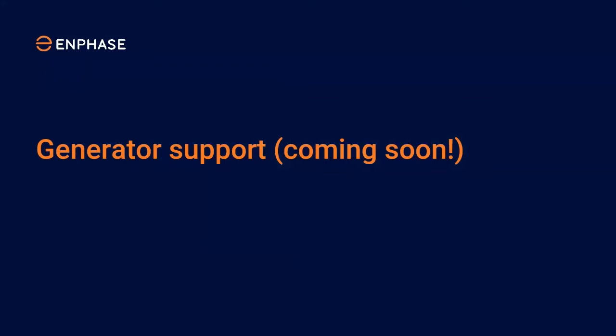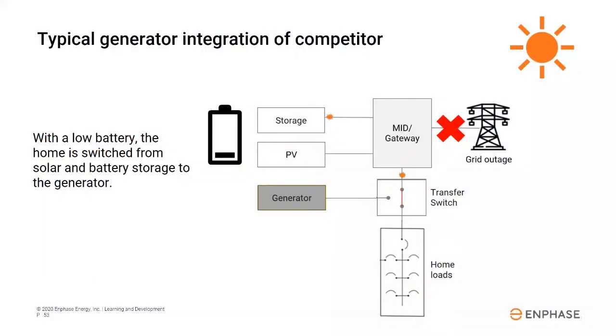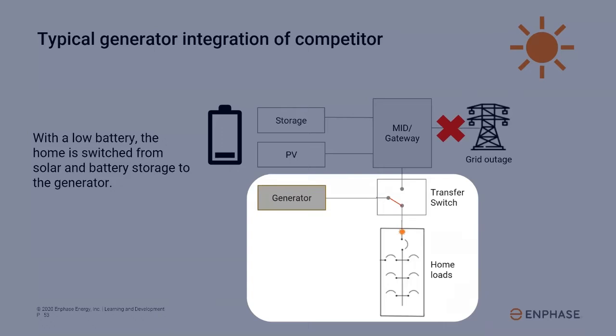Okay, lastly, I'm going to touch on generator support because this is a feature that's coming out soon, and the way that Enphase does generator support is pretty sophisticated compared to other companies. Typical configurations will use an external automatic transfer switch or even a manual transfer switch, which allows either the solar and storage system or a generator to power the house, but not at the same time. When a battery gets to a low state of charge, it'll automatically switch the home's power source to the generator, which is going to continue to power the home exclusively by itself. So the generator is going to power the home until the utility grid is back up, even if there's enough sunshine to power up the PV and the storage system. This means that the generator could run for many days, burning lots of fuel and causing a lot of unnecessary wear and tear.